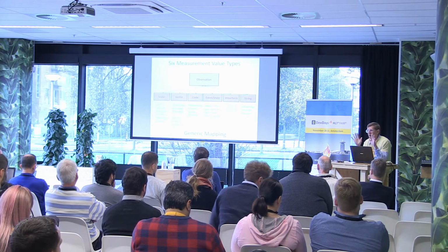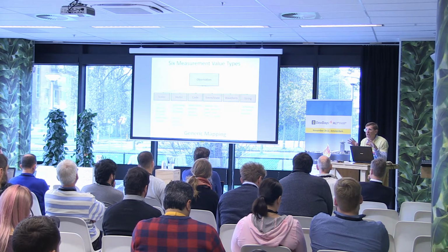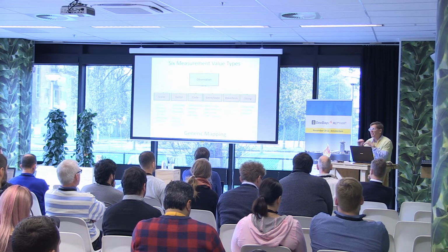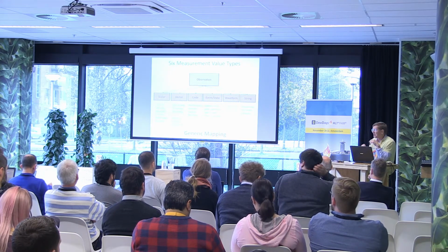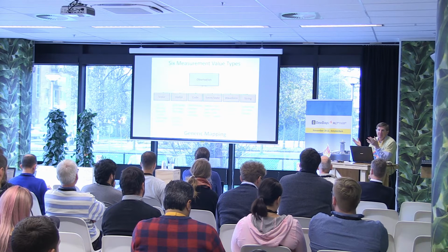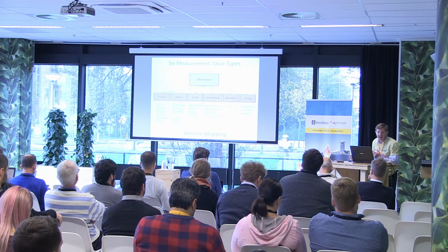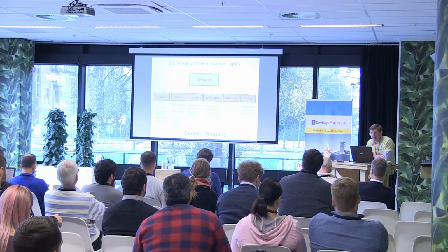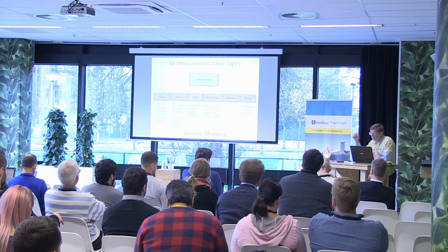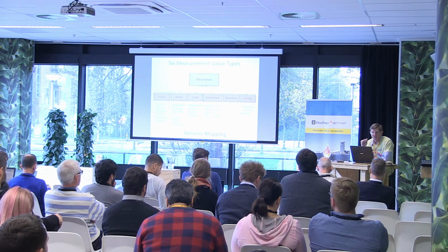mean. Now, I'm not going to try to fight about whether or not the blood pressure measurement should have been a compound measurement or a vector measurement or not. Somebody long before me decided, yes, this is the way we're going to represent it, and that's the way it was done. You could easily split it up, as you could split up any X, Y, and Z, and put an X measurement, a Y component measurement, and a Z component measurement as scalars. That can be done. But if it is represented on the device as a vector, we send it that way. And every such measurement is done in exactly the same way.